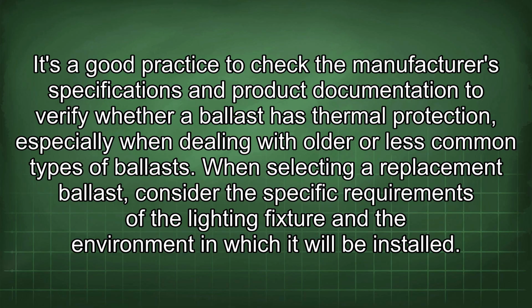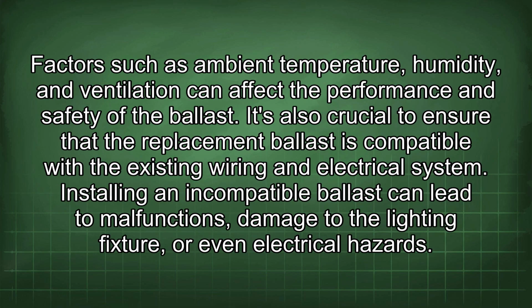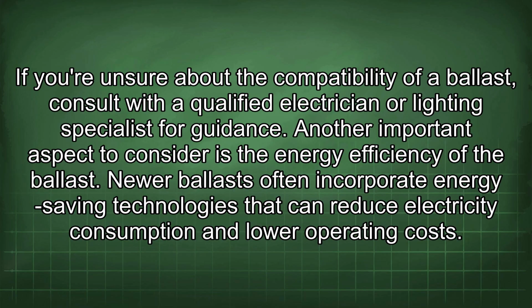When selecting a replacement ballast, consider the specific requirements of the lighting fixture and the environment in which it will be installed. Factors such as ambient temperature, humidity, and ventilation can affect the performance and safety of the ballast. It's also crucial to ensure that the replacement ballast is compatible with the existing wiring and electrical system. Installing an incompatible ballast can lead to malfunctions, damage to the lighting fixture, or even electrical hazards. If you're unsure about the compatibility of a ballast, consult with a qualified electrician or lighting specialist for guidance.